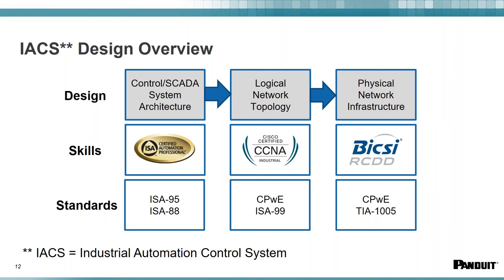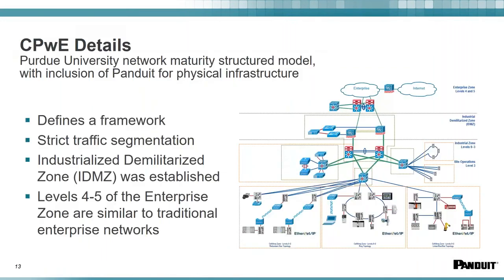And when you're dealing with low voltage communication, you could easily lose the 24 volts like 200 meters down the road, and you will not be able to send the signal. So you need to be aware that the TIA 1005 spec deals with that aspect of how can you get a signal, how can you get a packet, how can you get a communication stream from point A to point B within the factory systems.